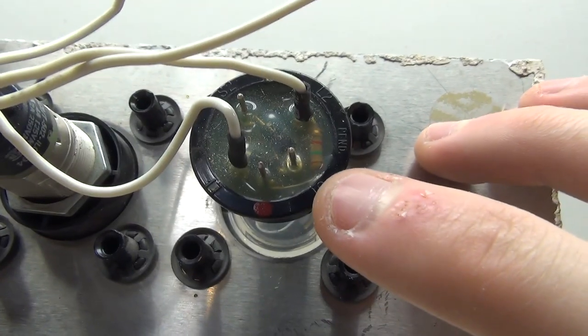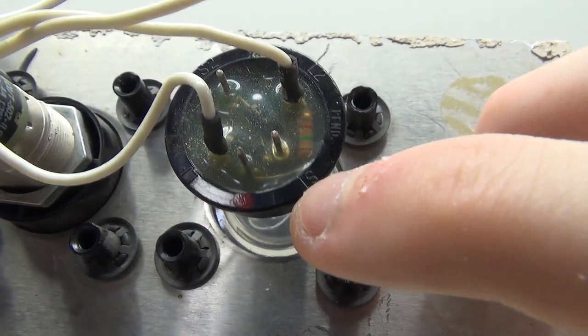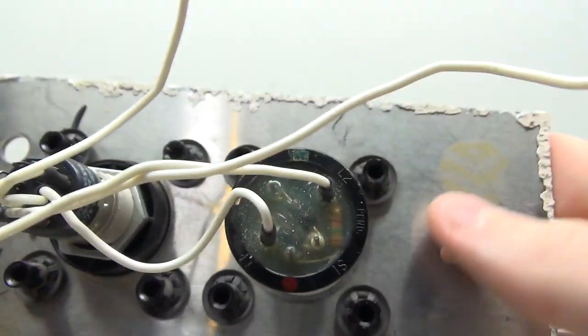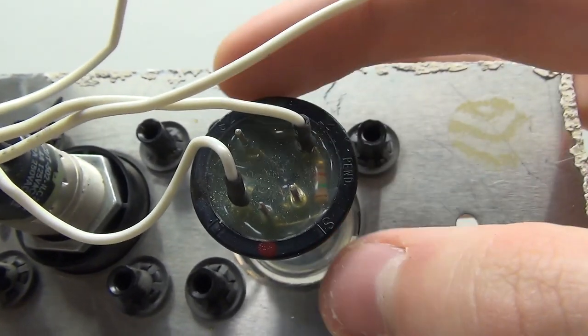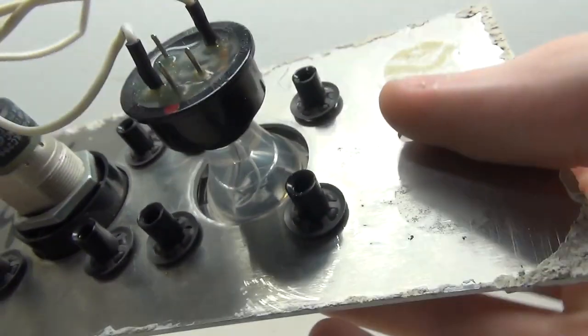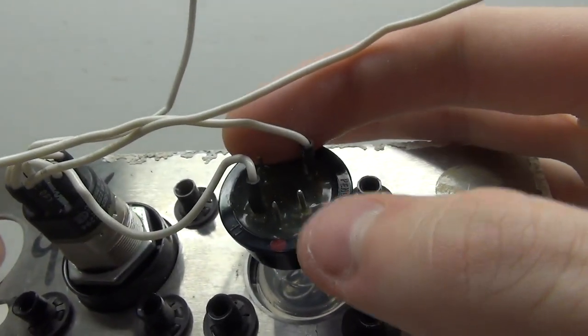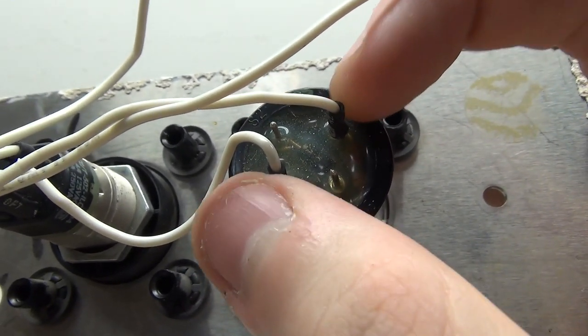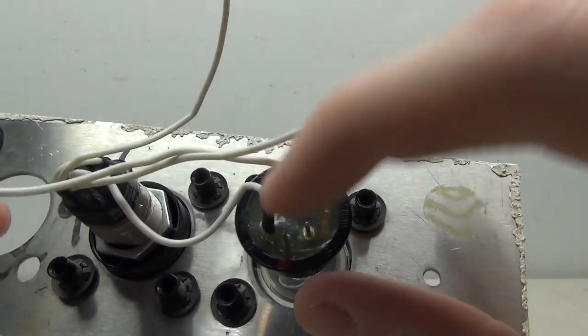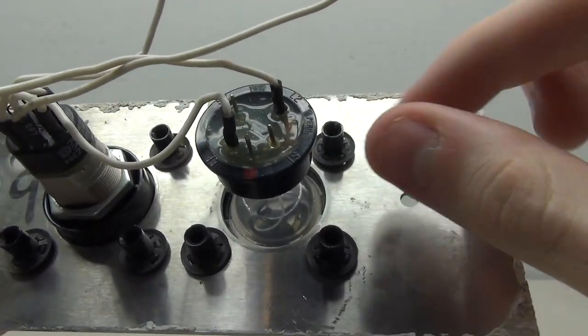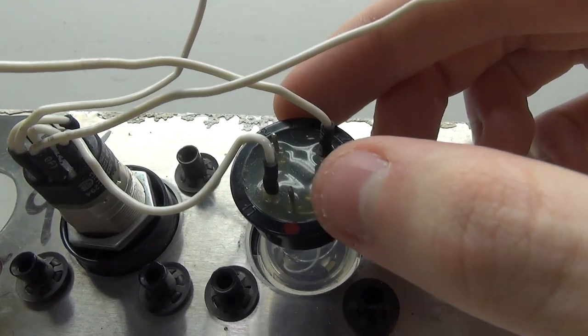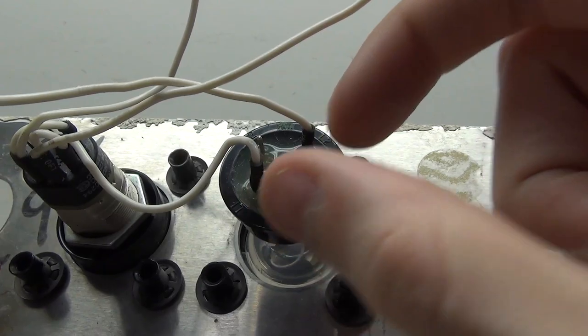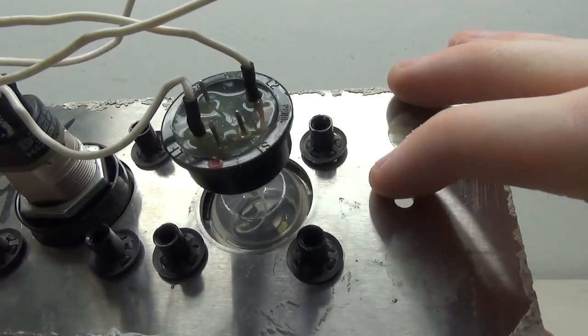On the back here we have these little pins, each with a corresponding letter and number - S1, L1, L2, S2. S2 and S1 are for the switch, so when you push the button in that's what is completed. L2 and L1 are for the light. This whole thing is 24 volts. For wiring we'll be using S1 and S2 for the switch part and then L1 and L2 for the light part.